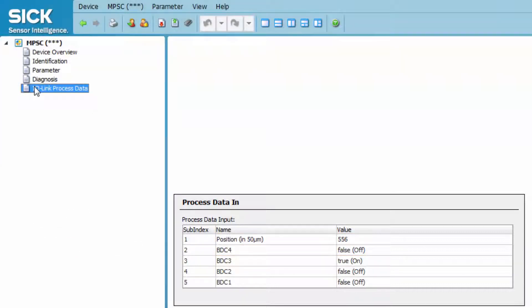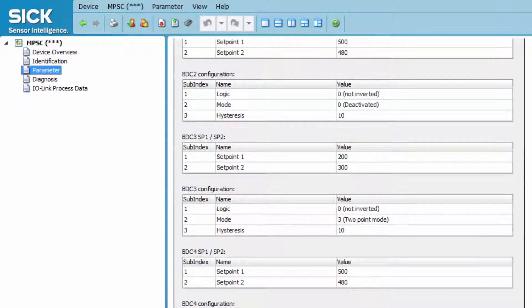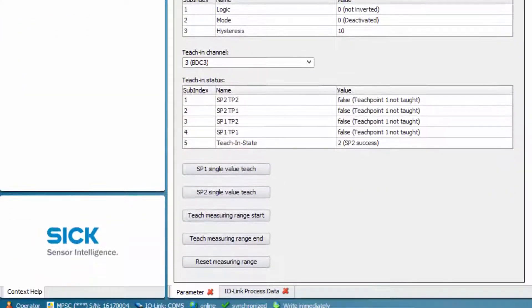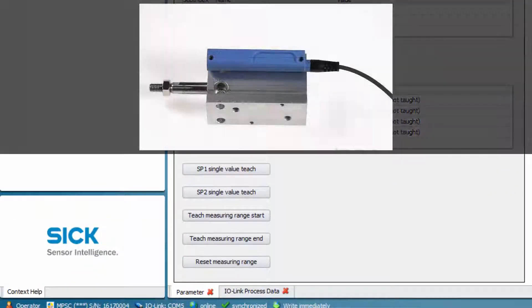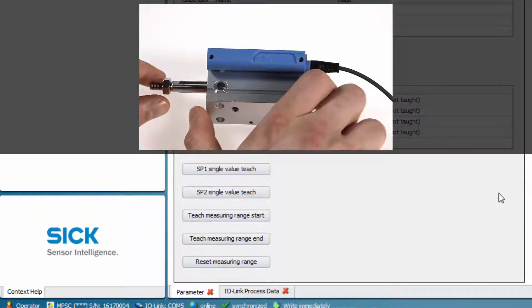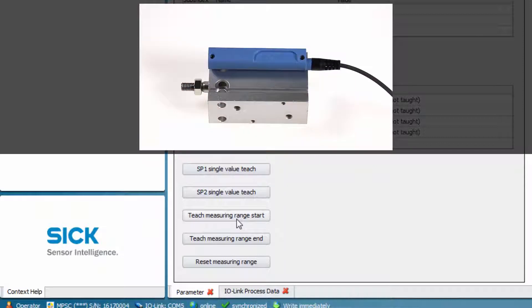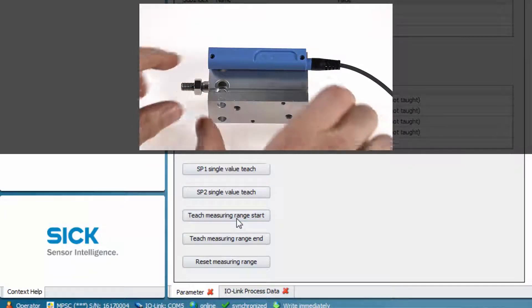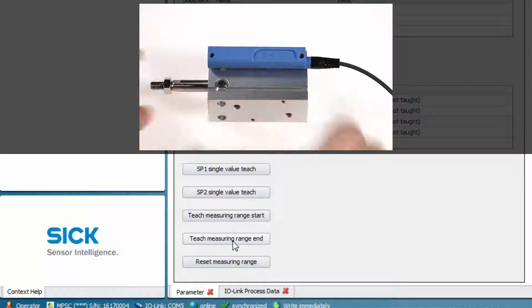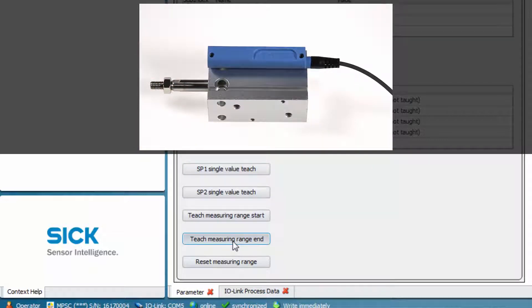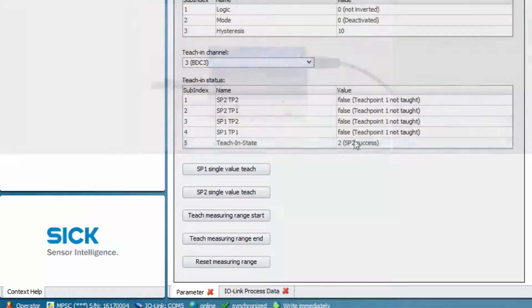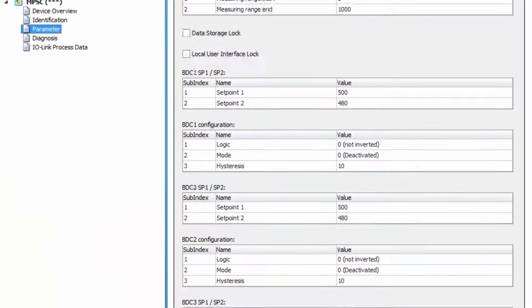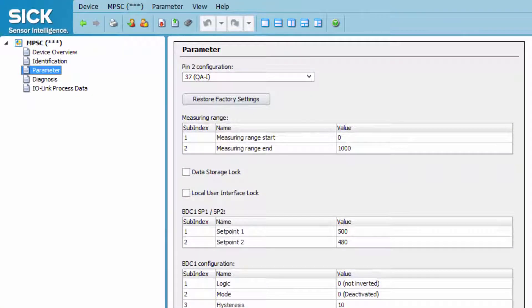To set the measuring range according to the needs of the application, move the piston into the start position of the measuring range and click the Teach Measuring Range button. Then move the piston to the end of the measuring range and click the Teach Measuring Range End button. Clicking on the Read from Device button will show the adjusted range in the Measuring Range section.